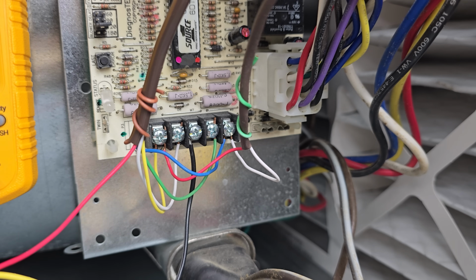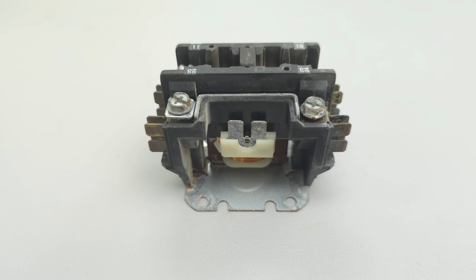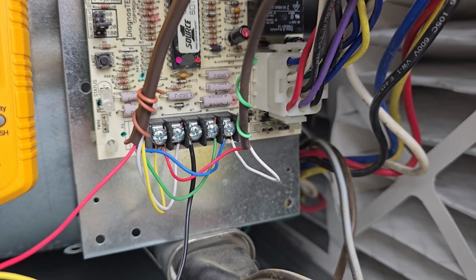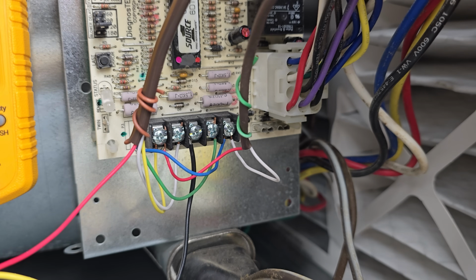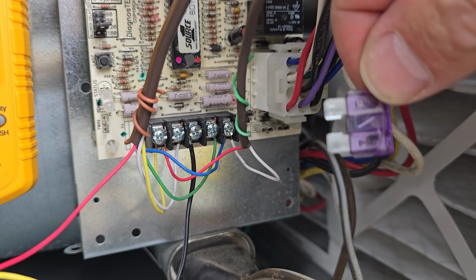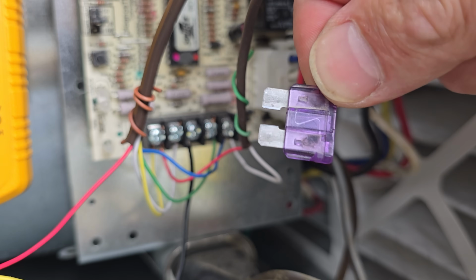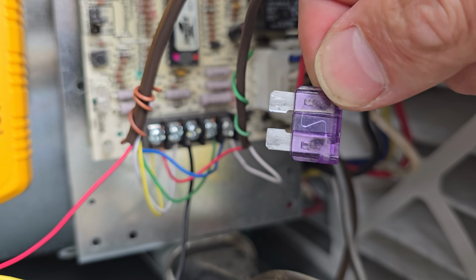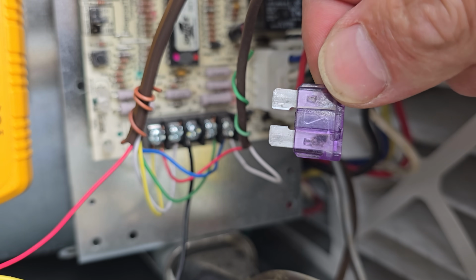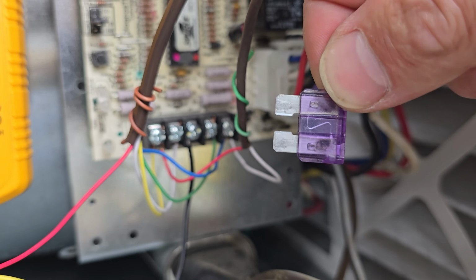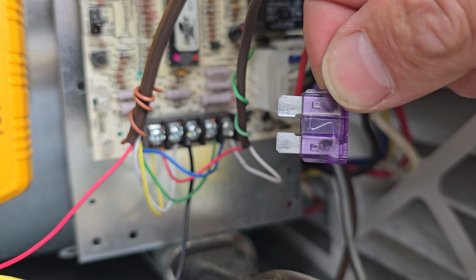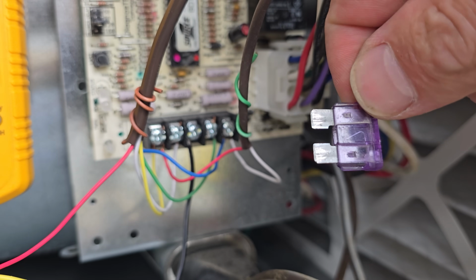It could also be that there's a device that's shorted the ground, so you have several different things that it could be. But this fuse is worth checking, and you just want to make sure to not just keep putting a new one in every single time and then having it blow. During the troubleshooting, there's a way to separate the wiring and things and measure electrical resistance until you figure out what the problem is. But check out our other videos in reference to that.